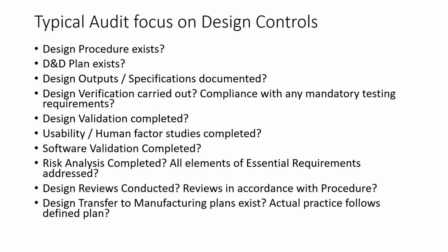What would they typically look at? Do you have a procedure? Do you have a plan? Have you documented design outputs? Is design verification done? Is validation completed? Have you taken into account usability and human factors? If software is involved, has software validation been done? What about risk analysis? Show me your risk analysis. How do you do design reviews and design transfer to manufacturing? What is your plan and what is your actual practice?